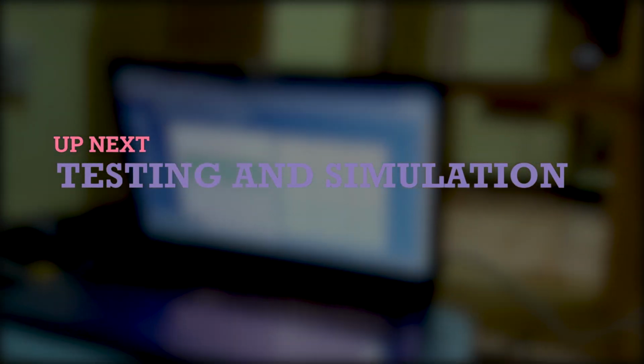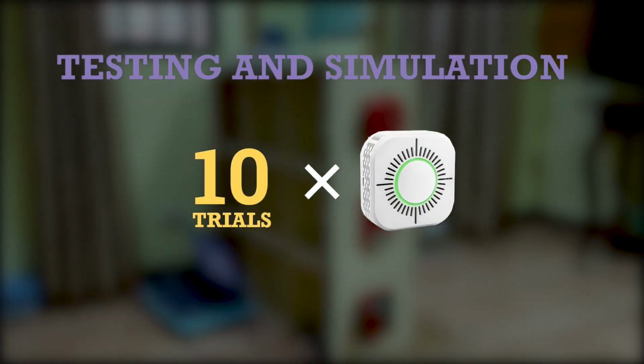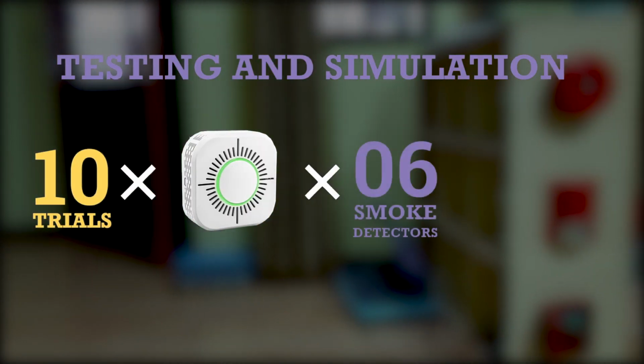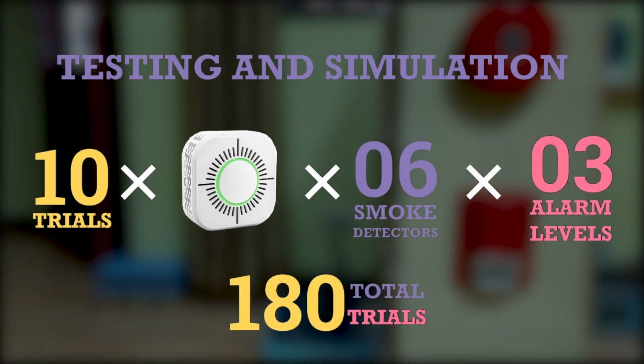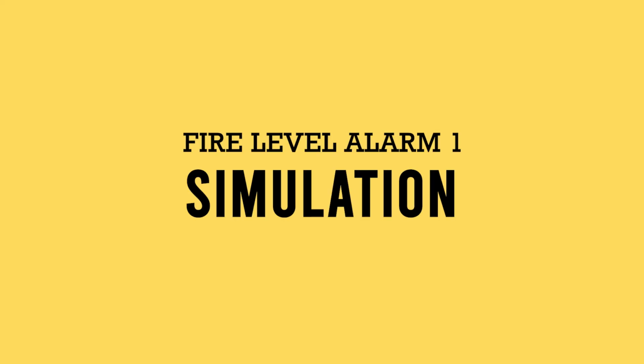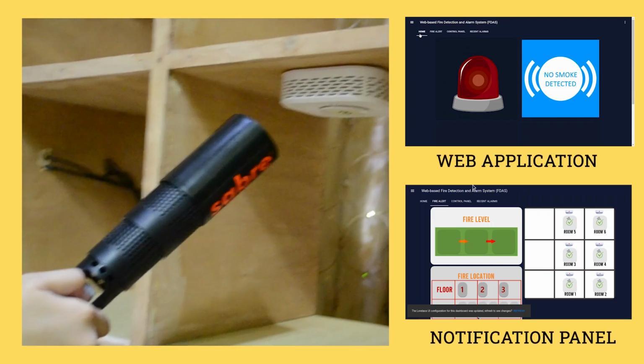In the next few video clips, we will show you how we simulated our tests and gathered our data. Simulations of all 3 levels were done in 10 trials for each smoke detector, which resulted in a total of 180 trials. To simulate the first fire alarm level, we must trigger 1 smoke detector. In this case, we chose smoke detector number 3.